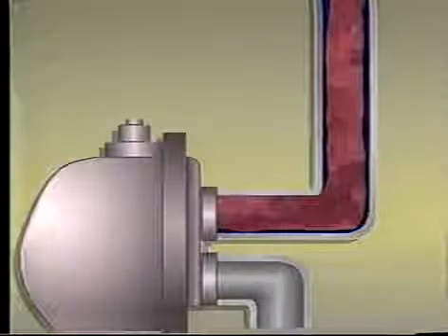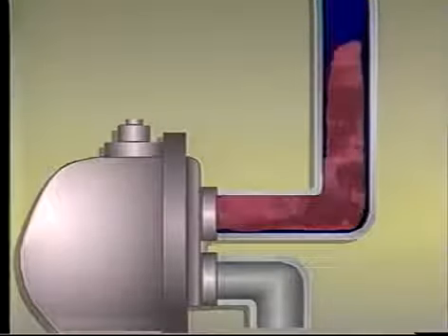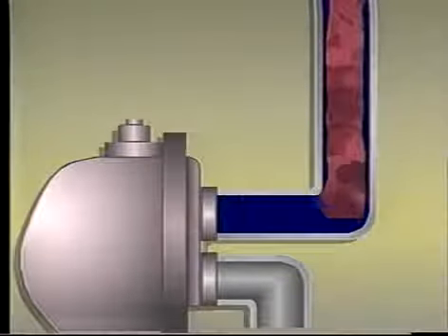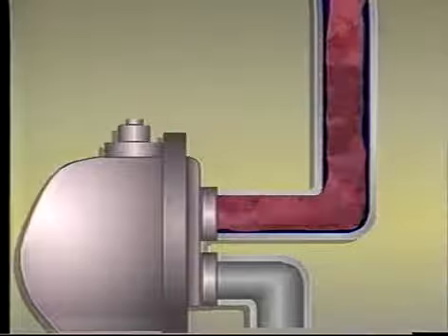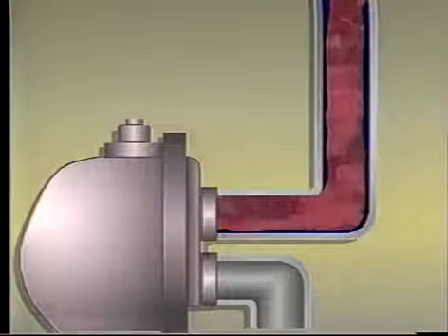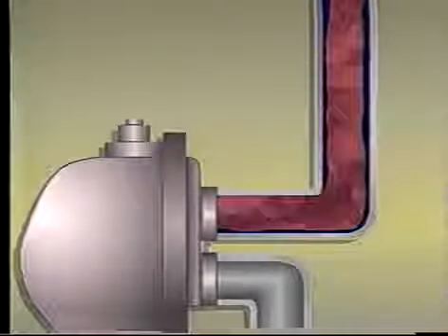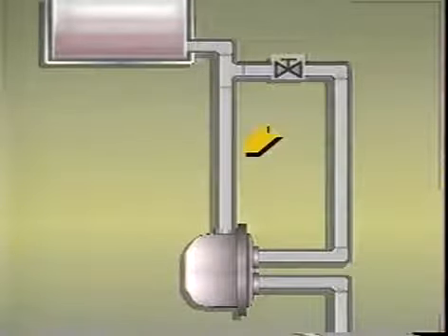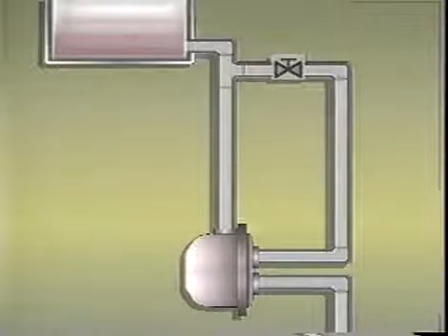If a slug of condensate seals off the pipe, steam collapses downstream of the seal. Again, a pressure differential forms, and this, along with gravity, accelerates the slug. When this piston strikes the trap, it can damage a float, the thermostatic element, or other parts of its mechanisms. To avoid differential shock arising from this situation, use an F&T trap and backvent it to the top of the vertical line to maintain near equal pressure throughout the riser, even if a slug of condensate forms.